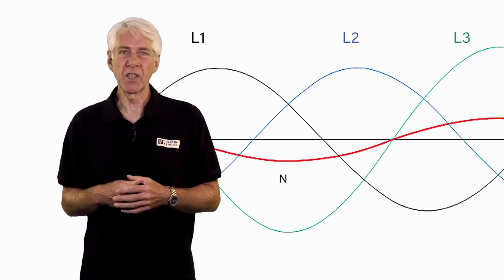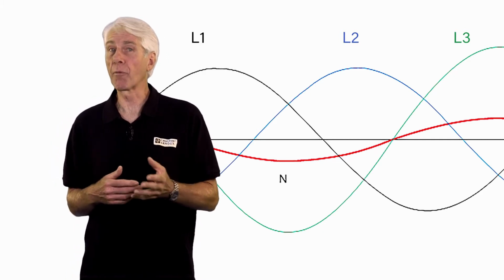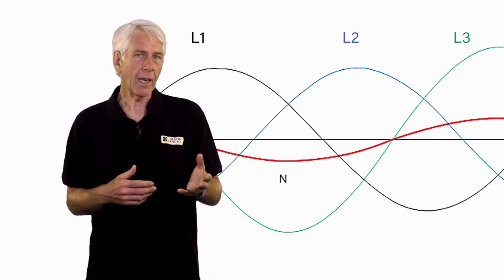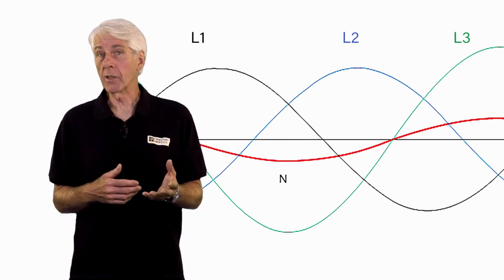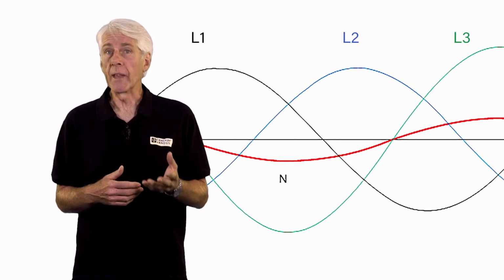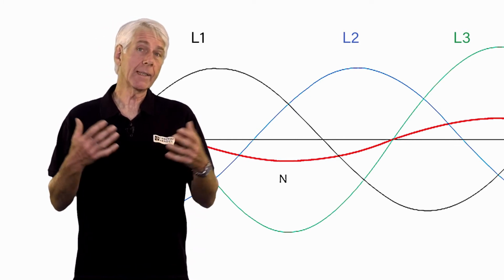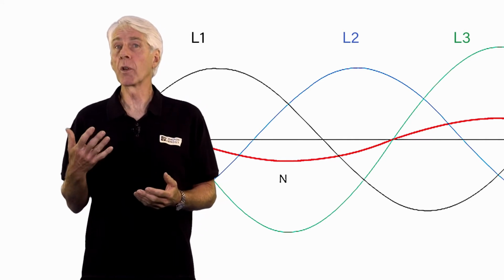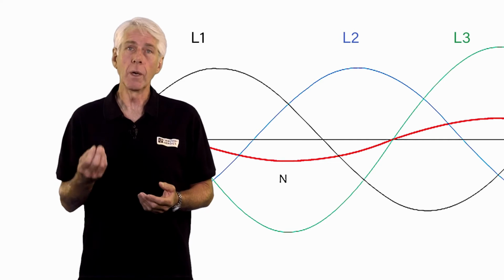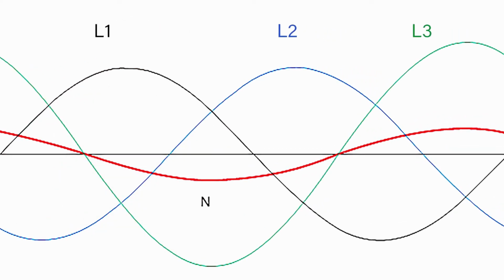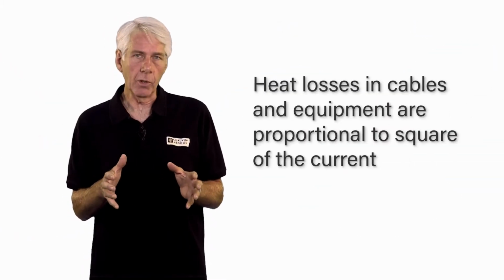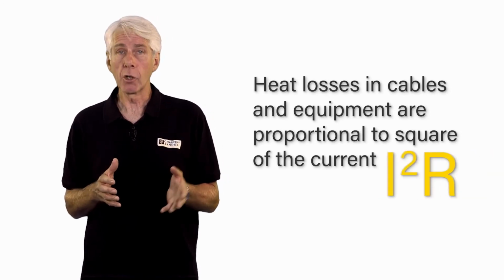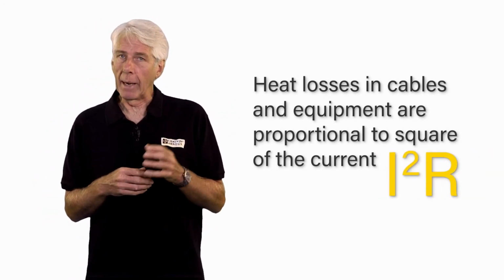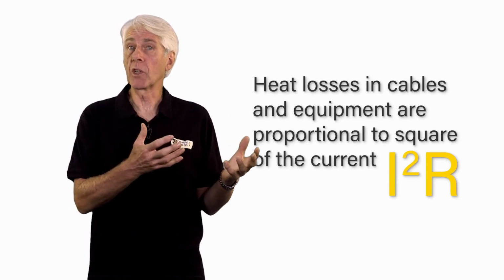Phase imbalance occurs when single-phase loads are unevenly balanced across the three phases of an installation. Often, like power factor correction, the phase loadings would have been balanced and checked when a facility was first designed, or when the initial installation was performed. But as time passes, it's common for the original loads to be moved or decommissioned, and new single-phase loads introduced. Now, if this is done without consideration or knowledge of the load spread across the three phases, then over time, significant imbalance will occur. Heat losses in cables and equipment are proportional to the square of the current, using the formula I squared R. Imbalanced phases mean high currents on phases that should be shared better across the others.